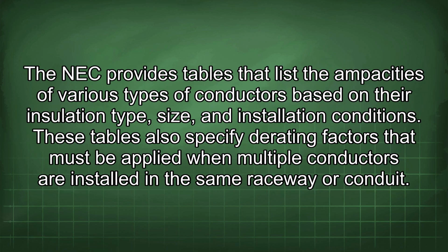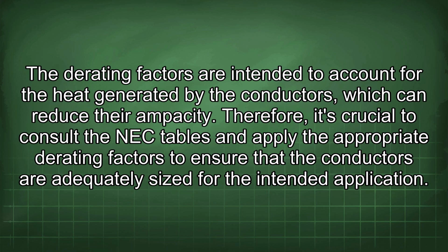The NEC provides tables that list the ampacities of various types of conductors based on their insulation type, size, and installation conditions. These tables also specify derating factors that must be applied when multiple conductors are installed in the same raceway or conduit. The derating factors are intended to account for the heat generated by the conductors, which can reduce their ampacity. Therefore, it's crucial to consult the NEC tables and apply the appropriate derating factors to ensure that the conductors are adequately sized for the intended application.